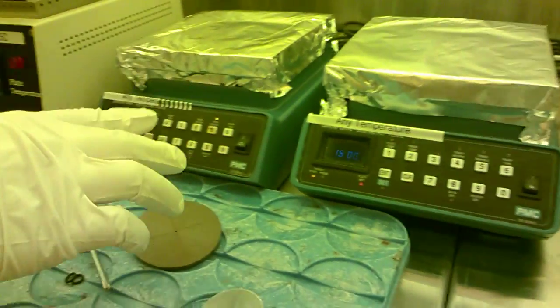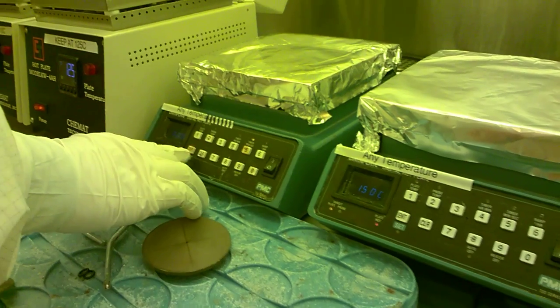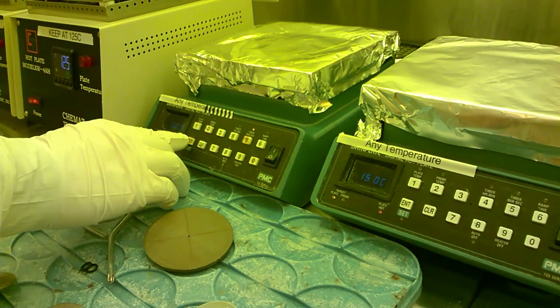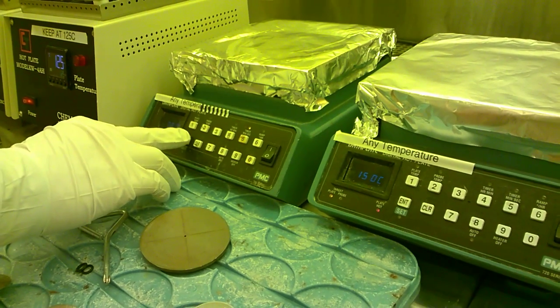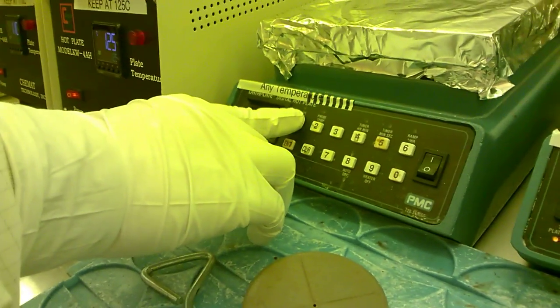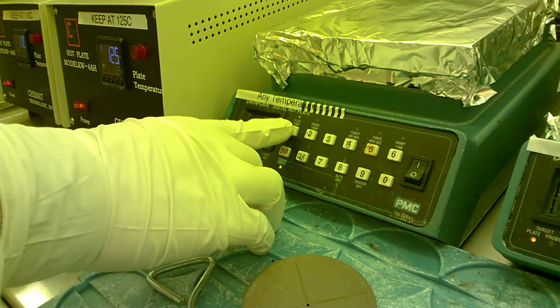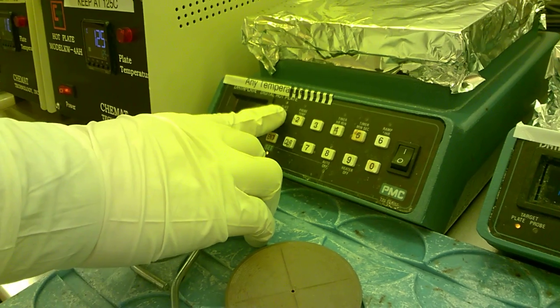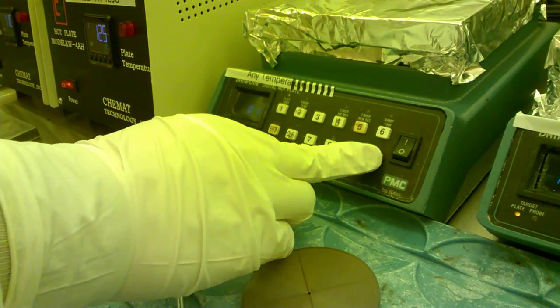This one is used for arbitrary temperature. You can set the temperature as you want. The operation is like this: you can look at set number one. Number one is the set temperature, and set whatever value you want. 100 is the set temperature.